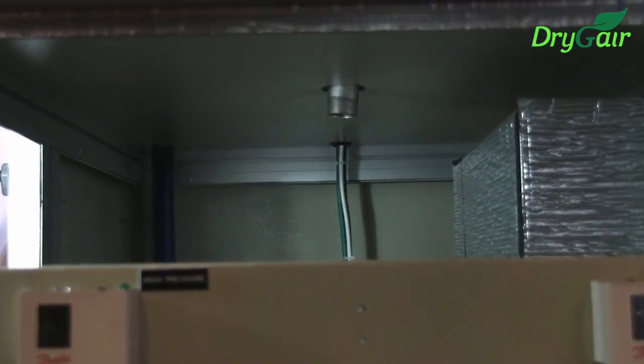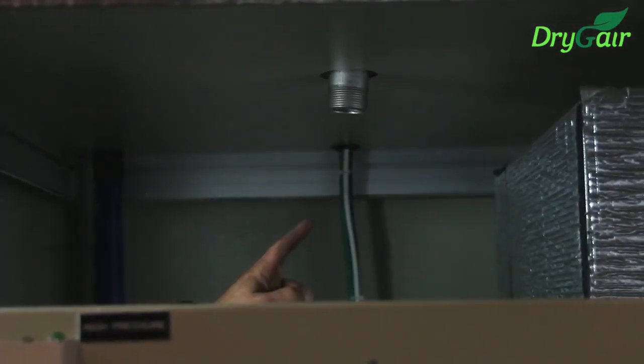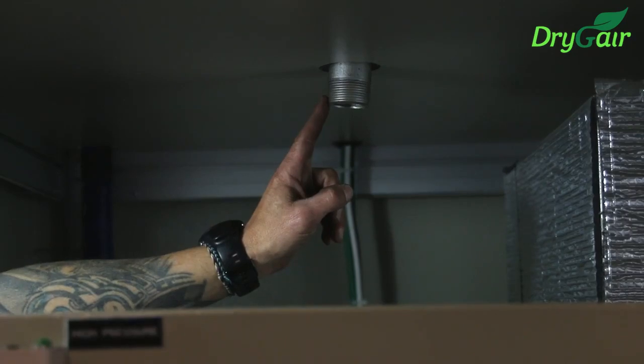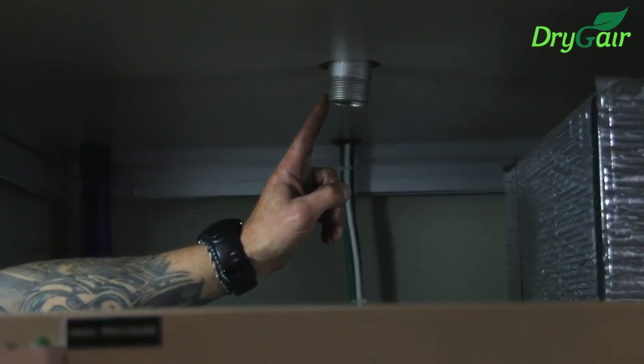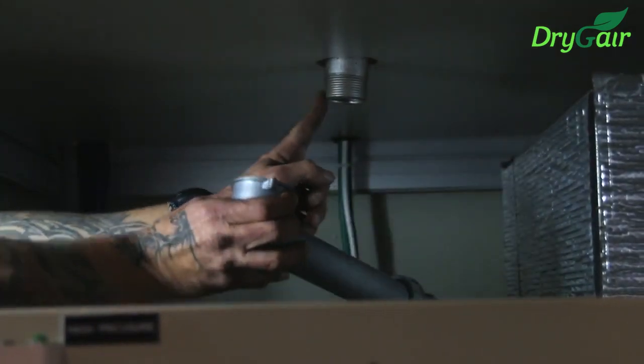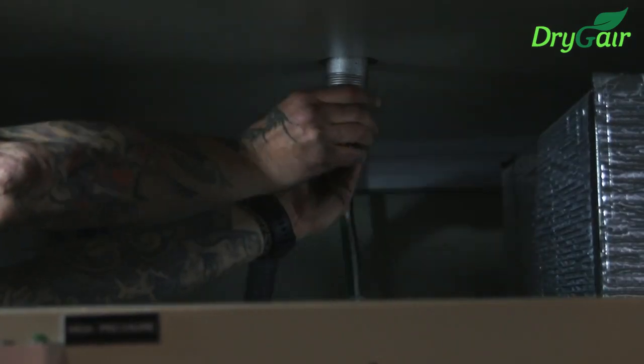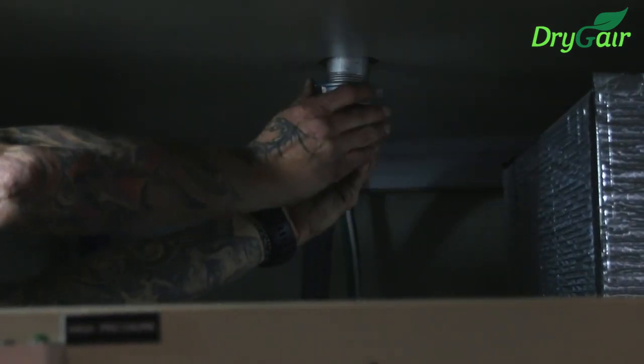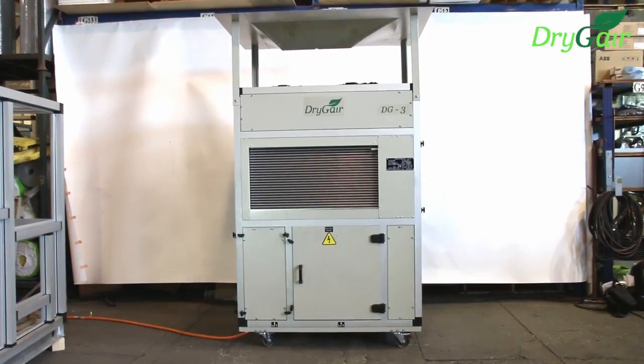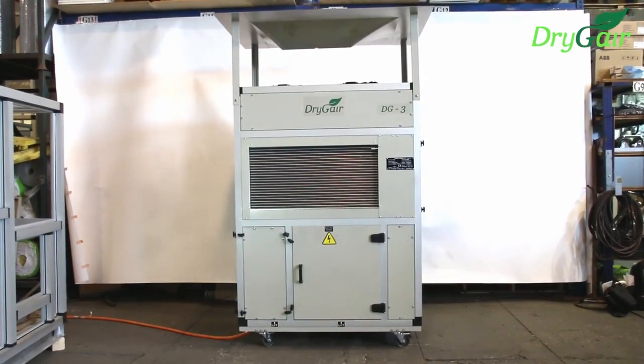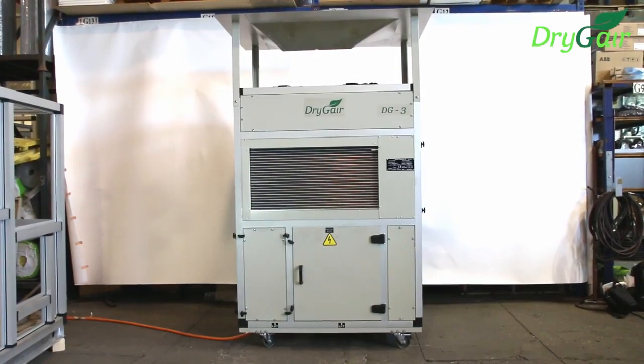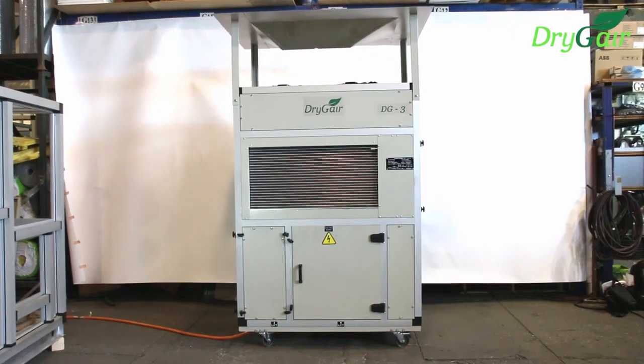To connect the drainage pipe, first remove the rear cover from the unit. Connect the prepared drain pipe with a siphon to the threaded 1.5-inch BSP bushing drain outlet. You can route the drainage tube through one of the 3 exits from the unit. The tube can be led out through the bottom from the floor beneath the unit.